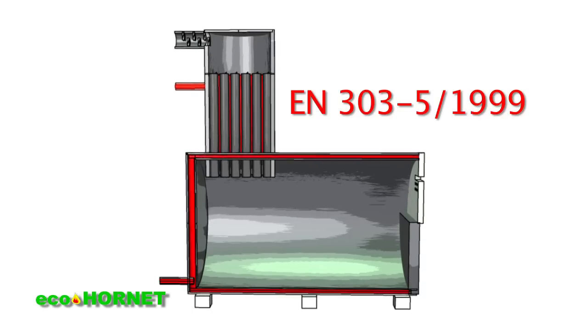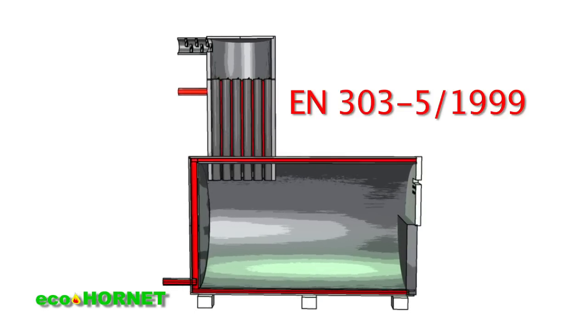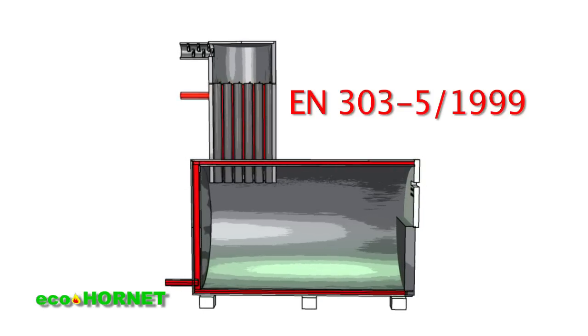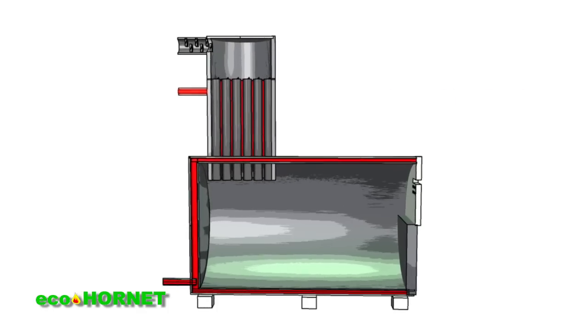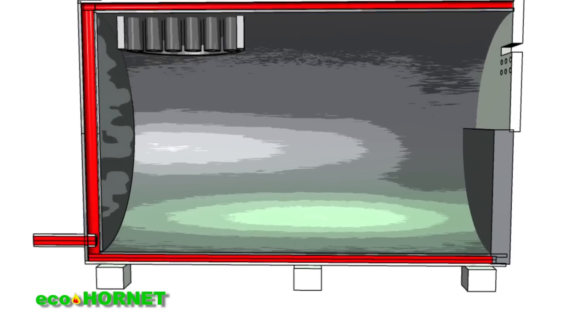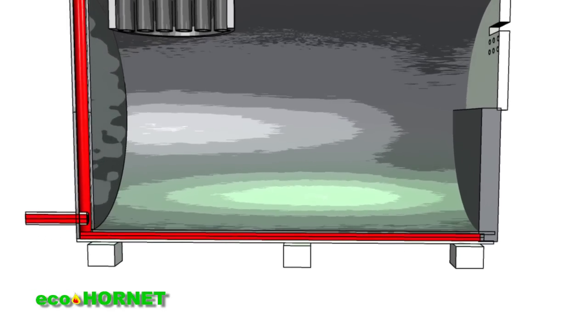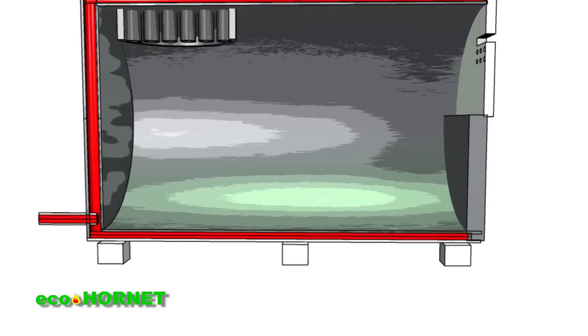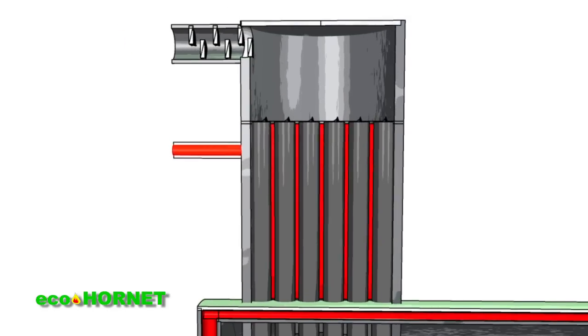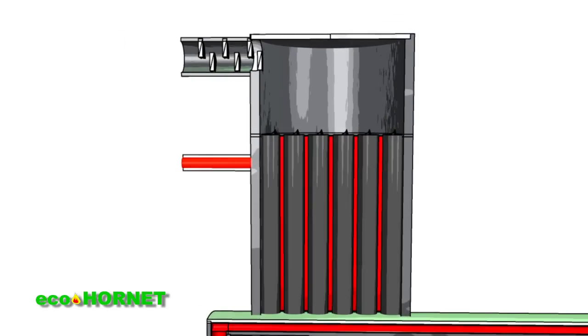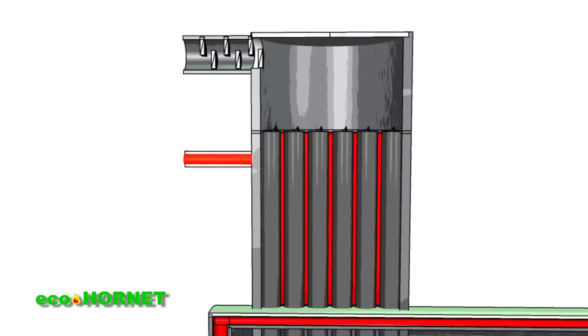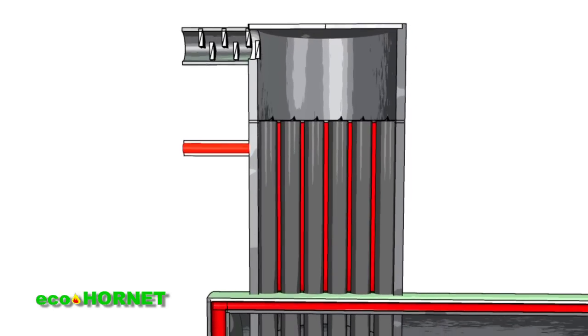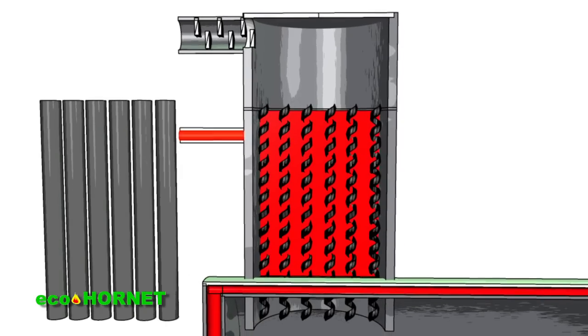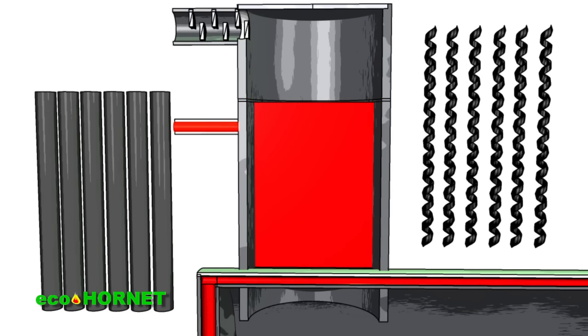The heat exchanger is made of steel, according to EN 303-5/1999, and has 2 distinct areas. A horizontal cylinder with double walls which circulates the heating agent, heated by radiation from the flame, and a vertical cylinder area in association with a horizontal area, which houses a number of pipes for burned gas called the convection area. Metallic spirals are inserted in the tubes for vortex generation and gas routing.